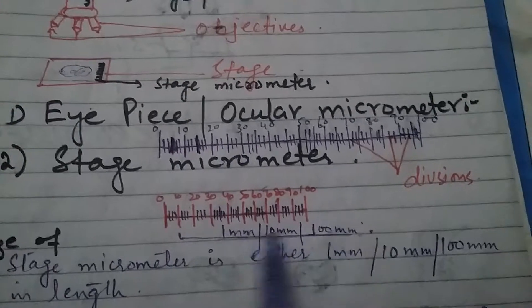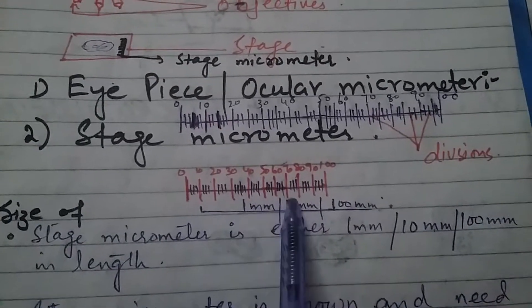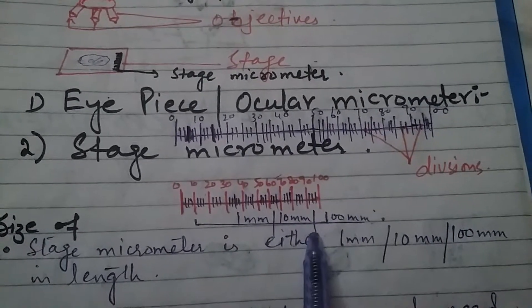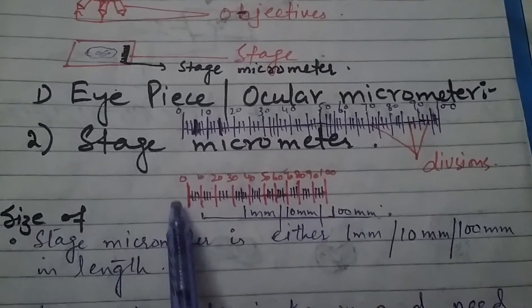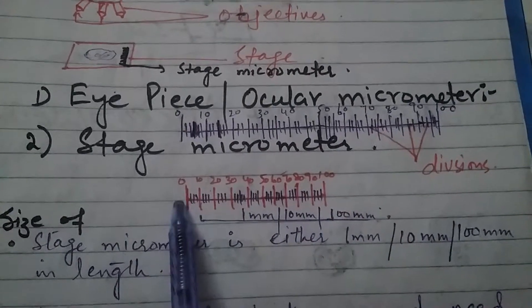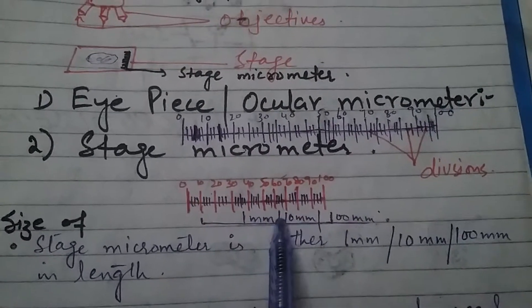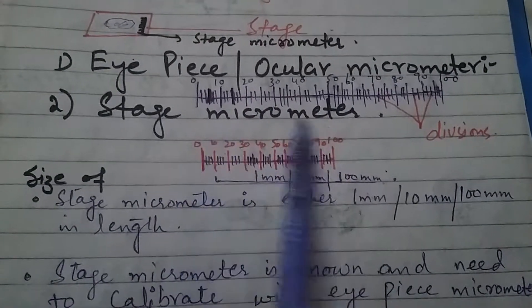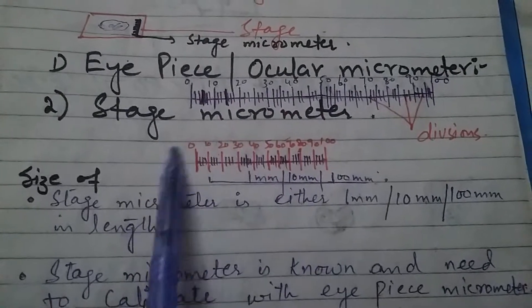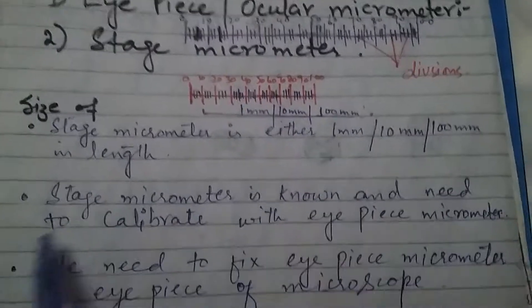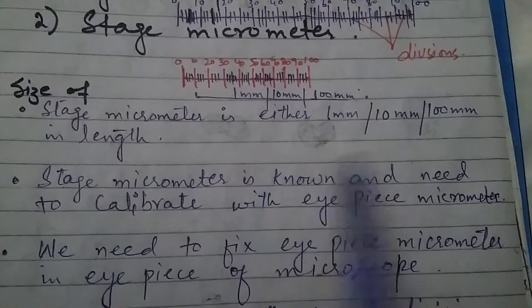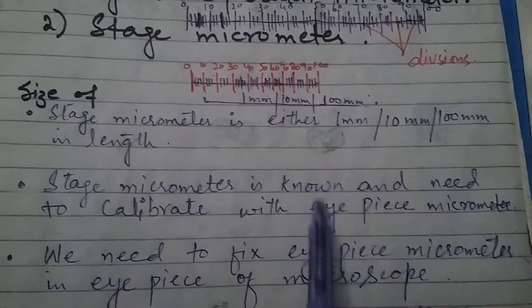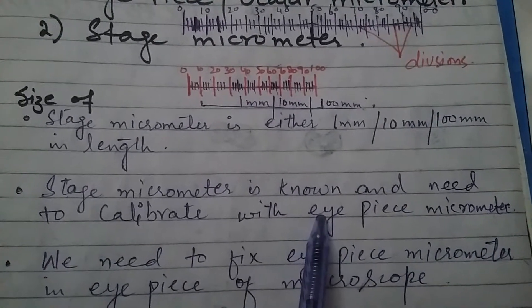The stage micrometer may have 100 divisions. The length of the stage micrometer is either 1 millimeter or 10 millimeter or even 100 millimeter. The stage micrometer is a known scale, and we use it to calibrate the eyepiece micrometer — we compute the alignment of the eyepiece micrometer divisions against the stage micrometer.